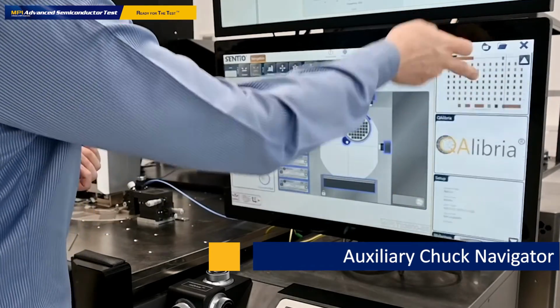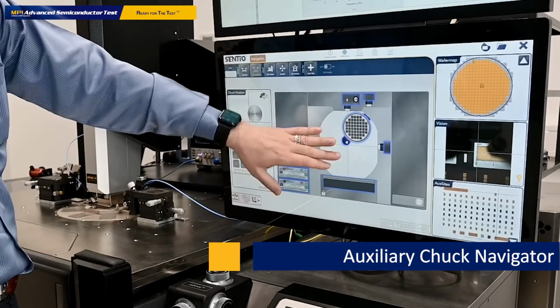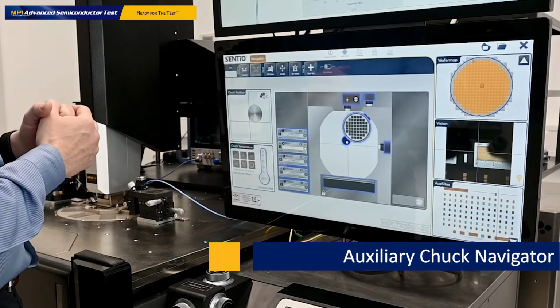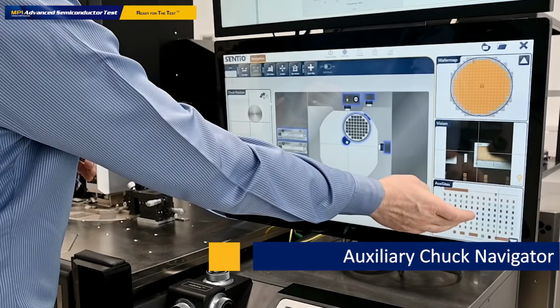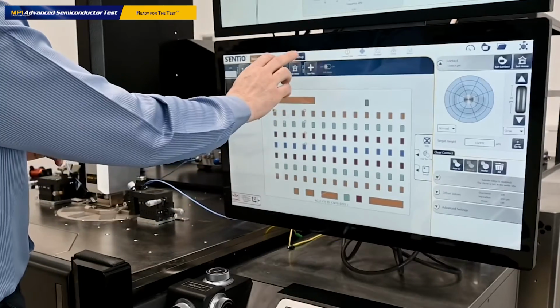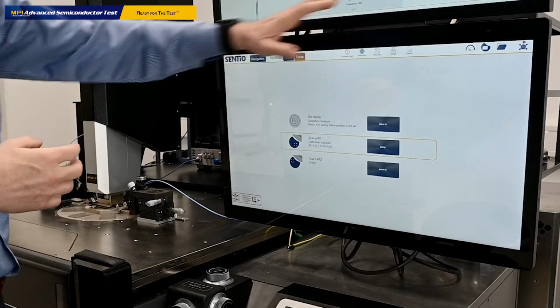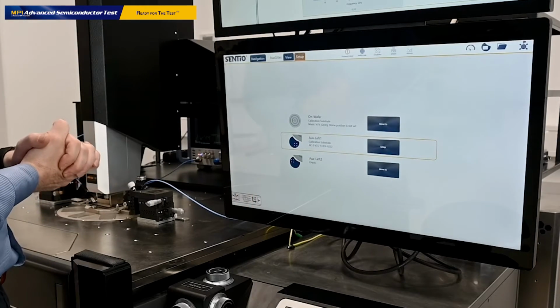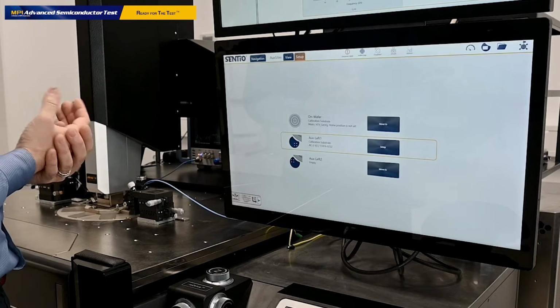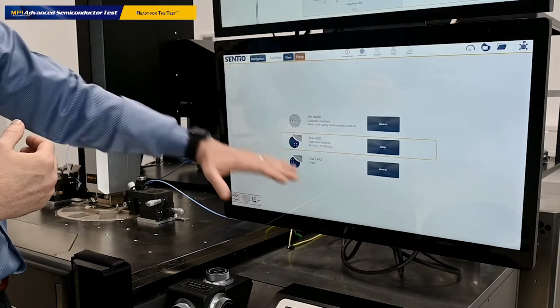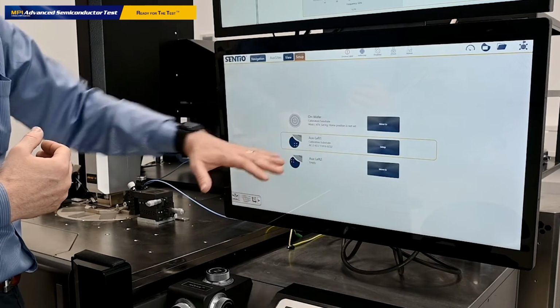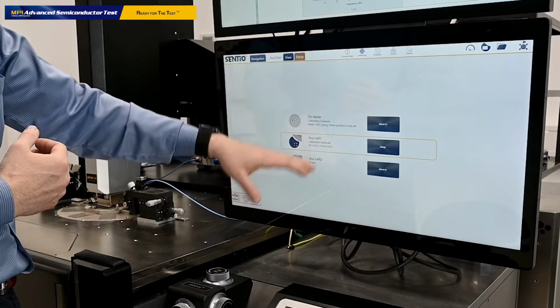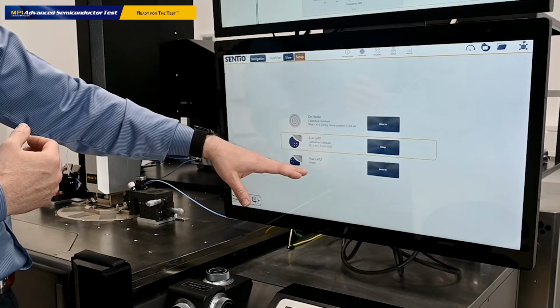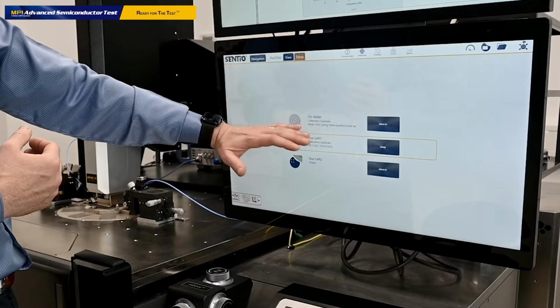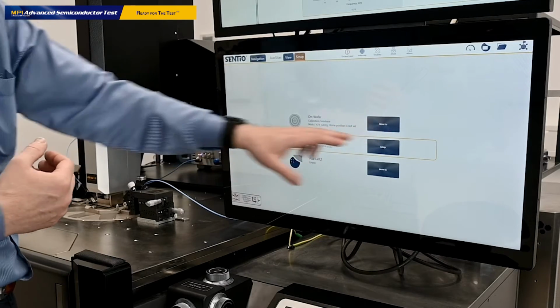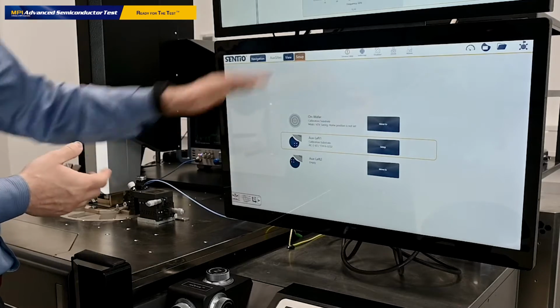So on the Sentio dashboard, we see that we are currently over the auxiliary chuck, and let me switch to the auxiliary site module and start the initial setup procedure. On the initial setup procedure, the first screen helps us to define where we are going to set up our calibration process. What you see here is that we currently have two auxiliary chucks available for RF calibration on the system, auxiliary left 1 and auxiliary left 2. Auxiliary left 2 is currently empty, and we also can set up calibration process for on-wafer calibration standards. That is the very first selection.